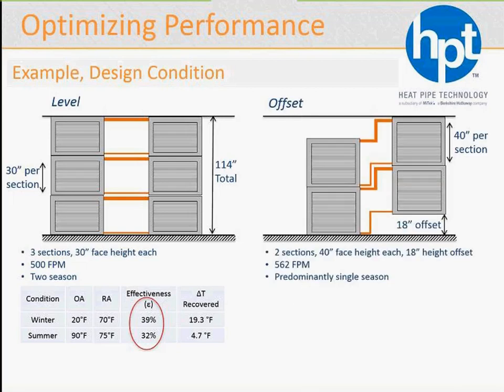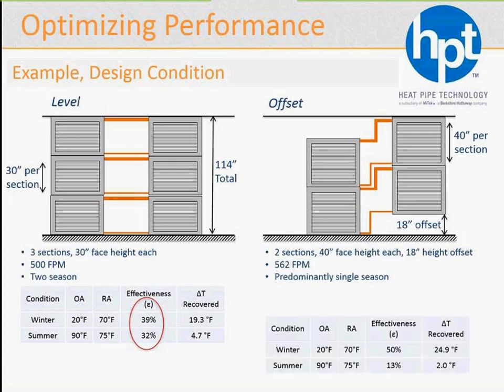If we do an offset, we actually get away with fewer sections, but what that means is the air would be squeezed into a tighter area, so the face velocity increases a little bit and the static pressure is a little bit higher. So it might cost a little bit, but the improvement in performance will more than make up for this. Again, we're showing a 25% offset to get this increased performance.